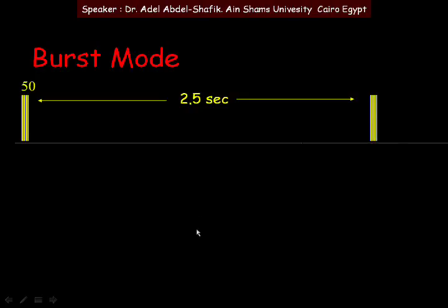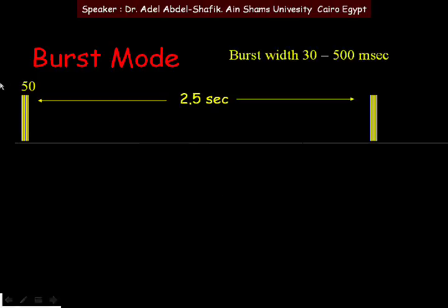The third mode is burst mode. In burst mode, you get a burst of ultrasound, then a long period of no ultrasound, then another burst. You can adjust the width of the burst between 30 to 500 milliseconds.